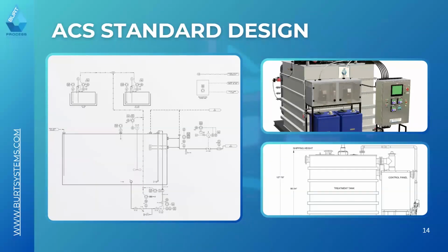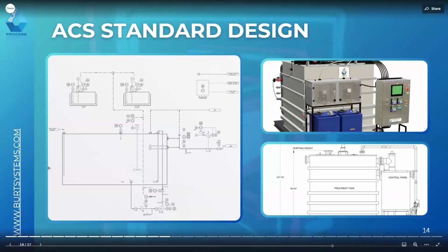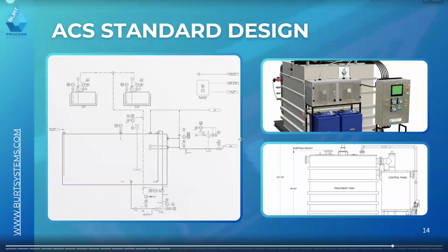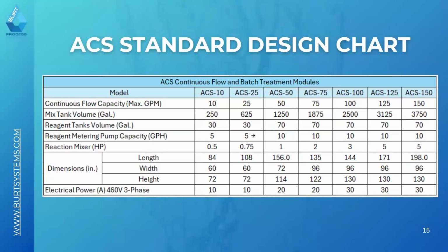This is the model. You can see the P&ID. It's really this double U-trap configuration where you have built-in residency time. This can also be done with a recirculation loop back into an EQ tank, which I'm obviously not showing here, but there are a lot of different ways to build that in. That's an important thing in any kind of critical infrastructure, like the pharmaceutical industry, where you want the ability to bring the waste back, or have some way to hold that waste and still allow for additional treatment. Because if the system goes down, everything upstream of it effectively goes down.